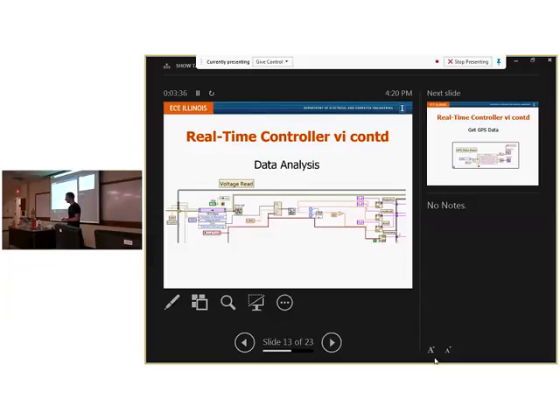So we sample at 10,000 hertz, and we report at 10 hertz. That means every 1,000 sample points, we extract the data, calculate the voltage magnitude, amplitude, and frequency, and use a timestamp to stamp our data. This happens 10 times a second.